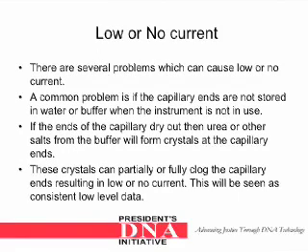Low or no current: there are several problems which can cause low or no current. A common problem is if the capillary ends are not stored in water or buffer when the instrument is not in use. If the ends of the capillary dry out, then urea or other salts from the buffer will form crystals at the capillary ends. These crystals can partially or fully clog the capillary ends, resulting in low or no current.